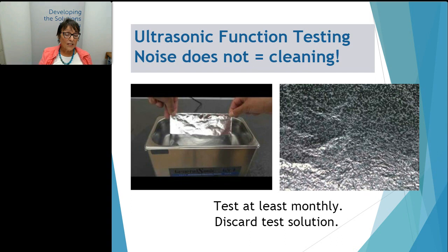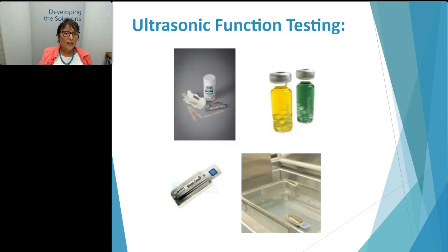Other types of function testing, which are a little bit more objective, are commercially available. There's various types of strips, coupons. There's a little SonoCheck capsule thing. There's a strip that actually tests for both enzyme content as well as the sonication process itself. But these are all basically function tests. They don't test that your instruments are clean. They test that your device is working.